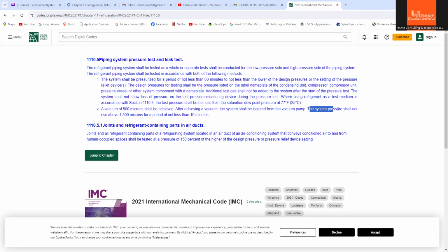And the tolerance: it shall not rise above 1,500 microns for a period of 10 minutes. It means if the refrigerant piping system reaches 500 microns, you time it for 10 minutes, and it should not be more than 1,500 microns after 10 minutes from 500. So the test is in conformance with the requirement as per this code.